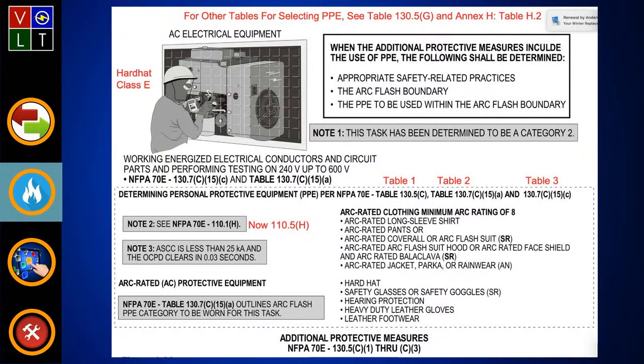After you selected your category from the second table, you go to the third table, 130.7C15C, which we've already looked at. Category 1 is 4 cal. Category 2 is 8 cal. Category 3 is 25 cal. Category 4 is 40 cal. Nice. Now, that's the second method, besides the table 130.5G that you could use.